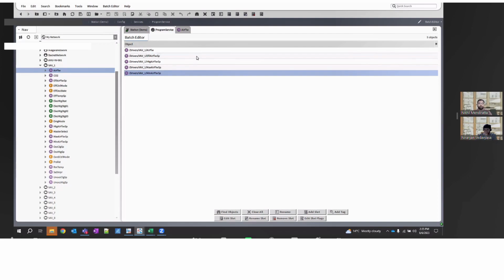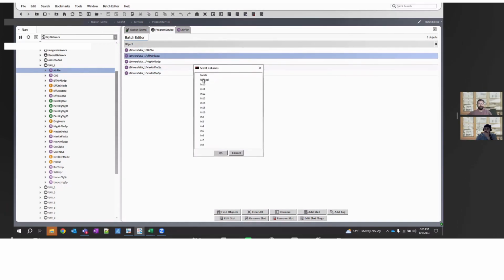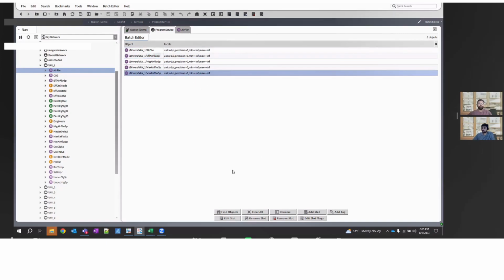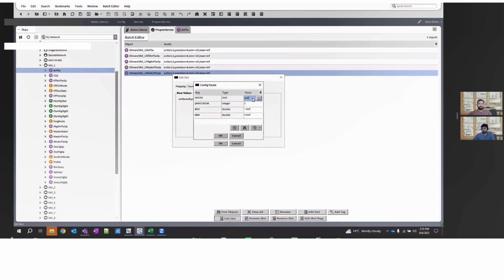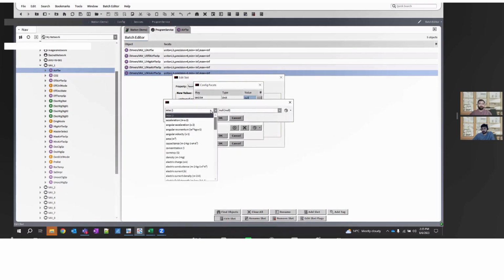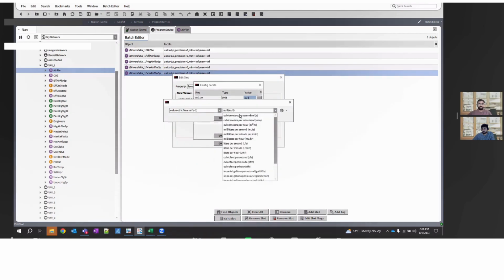Just for a quick view, you have select columns where you can choose what point properties to see, and if you want to see facets, you can choose facet — this gives an overview of the current facets. Now, to change it to CFM for Imperial units, I'll click on edit slot, facets, and new value. In units, I'll go to volumetric flow and change it to CFM.